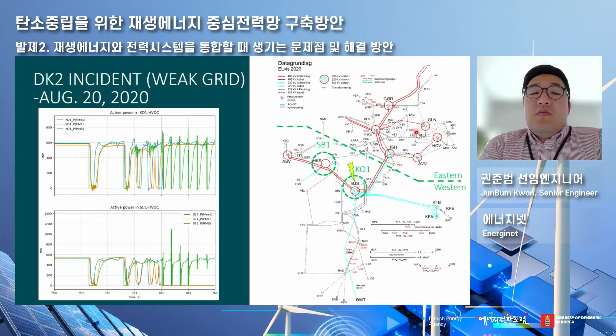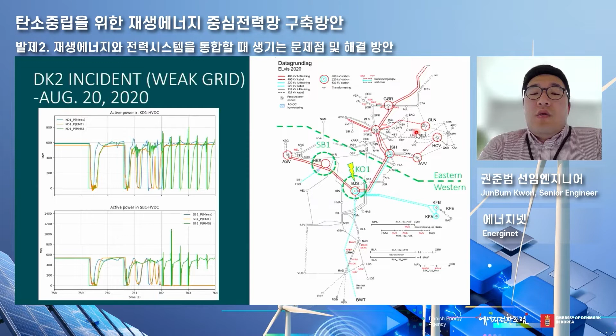What we realized from this incident was that the RMS model can be highly inaccurate for a weak system. So what we are working on now is EMT-based system-level simulation. There is a bandwidth that can cover both RMS and EMT. For strong grid-based, synchronous-dominated systems, RMS was enough, but for inverter-based systems, we need more EMT-type models.